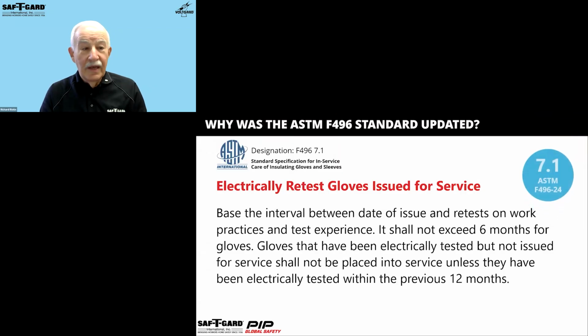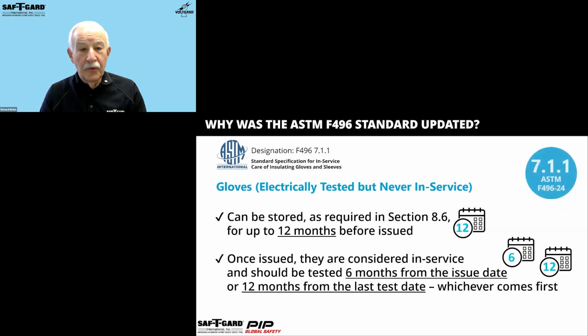What this says now is that the standard clarifies the difference between new gloves and gloves previously put into service, and makes it very clear that gloves cannot exceed 6 months from the last test or be electrically tested within the previous 12 months. That is 6 month intervals, and 12 months from the previous test if they were put into service and then stored again. Those are the dates. There should never be gloves in service that have more than 6 months from their issue date or 12 months from the last test date, whichever comes first.